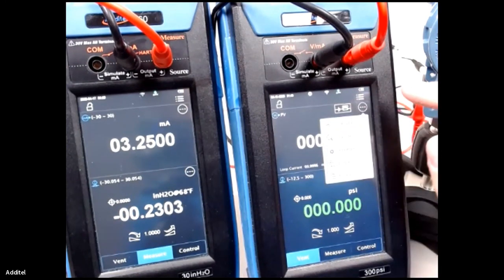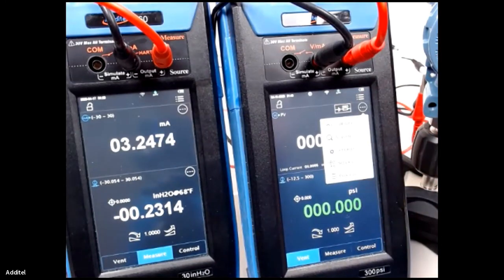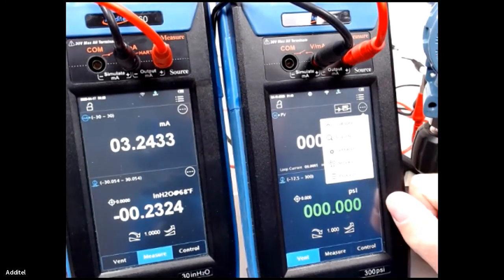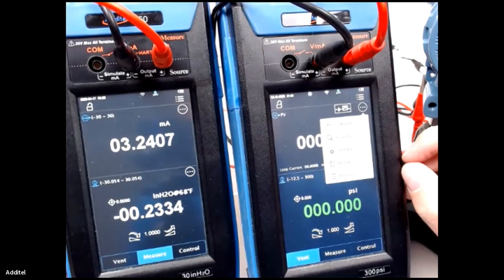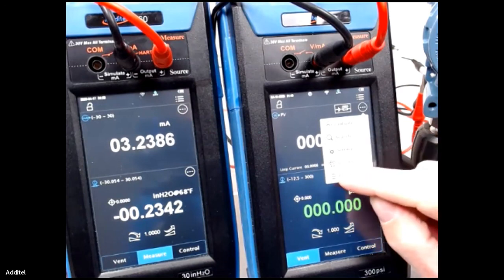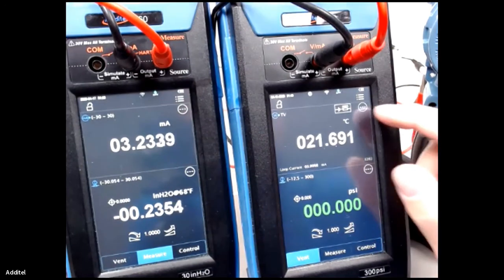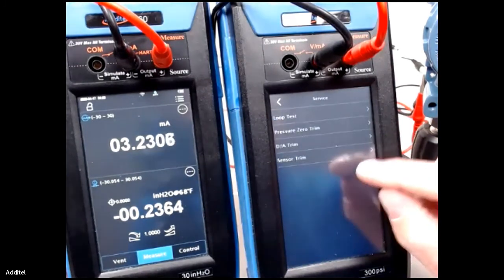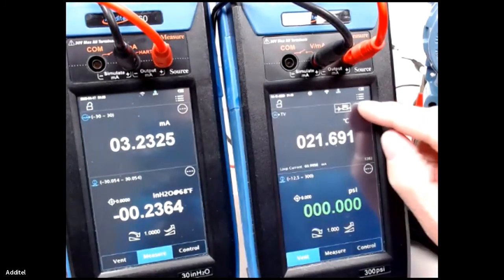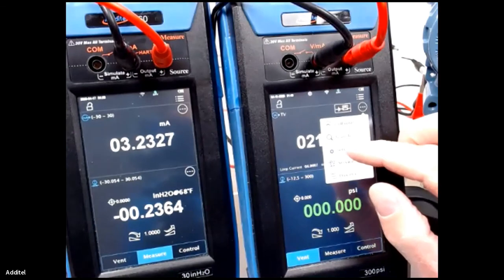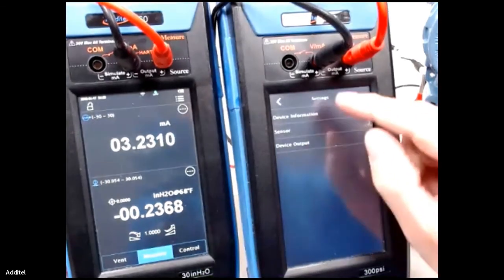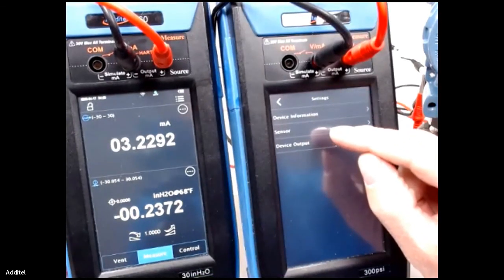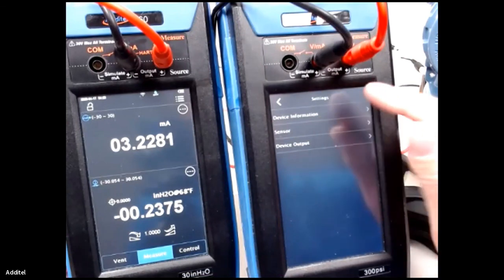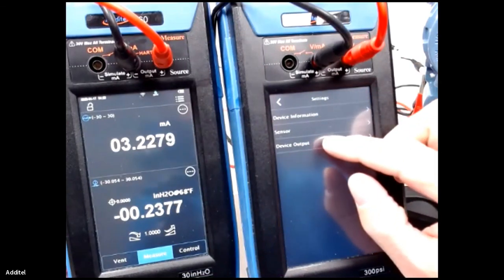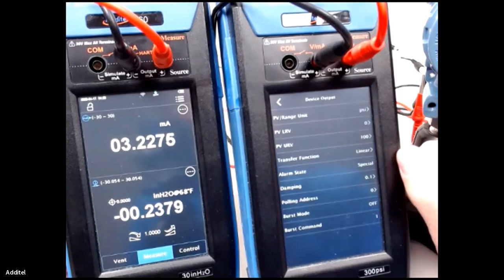That's one of the things people have really liked about this. But if I go in here and I want to adjust this HART transmitter, we can go in here and do that. Let's go into the process first and see what we've got. Let's go into settings first, so we can see our device output, our sensor, and our device information. Let's go into the output of this transmitter and see what it's set to.